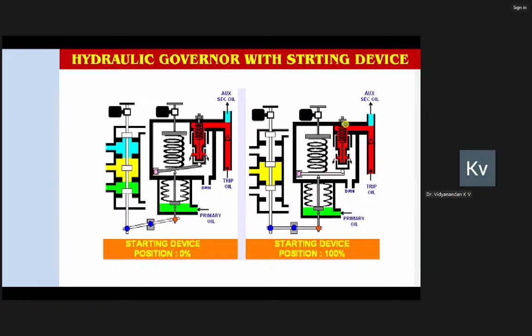Hydraulic governor consists of a speeder gear. Speeder gear means basically it's a combined effect of a spring and a bellow combinedly acting on a tiltable plate, which in turn regulates the drain port, that is the so-called auxiliary follow-up piston. So by bringing the starting device to the minimum position, that is 0 position, irrespective of the governor, whether your machine was earlier running on hydraulic mode or electro-hydraulic governor, if you bring down the starting device to 0, you will completely defeat or block the governor.